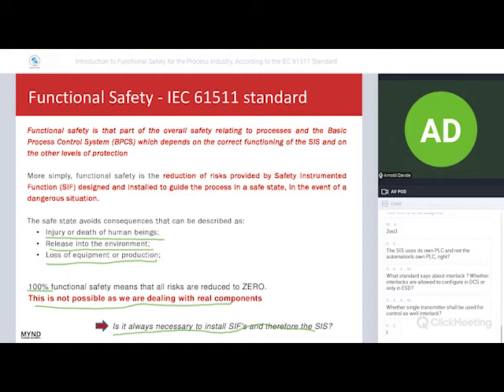No. Maybe it's not required, because maybe I have already installed or designed a lot of safety devices, and the safety devices reduce the risk to the tolerable zone. So why do I have to install a safety instrumented function just to complicate my life? Maybe it's not required, because it is sufficient to have a pressure safety valve. Why do I have to install a lot of hardware and spend a lot of money, and maybe the safety instrumented function installed where it is not required causes some problems for the process.